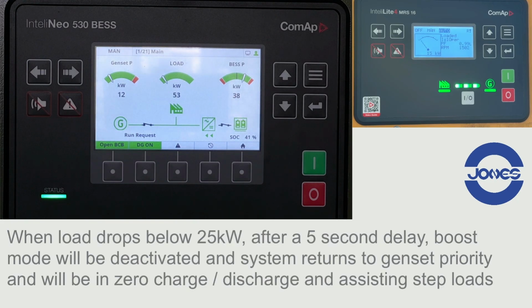For this setup, when load drops below 25 kilowatts, after a 5-second delay, boost mode will be deactivated and the system returns to Genset Priority and will be in zero charge discharge and assisting step loads.